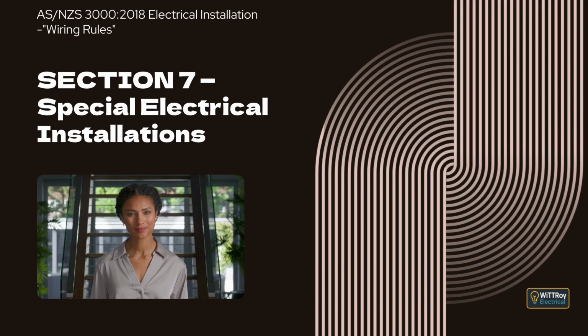Clause 7.2.5.1 General. This clause explains that fire pumps and fire pump control equipment include items such as fire hydrant booster pumps, pumps for automatic sprinkler or spray or deluge systems, pumps for fire hose reels where they are the sole means of fire protection, fire pump control equipment and wiring systems, and fire pump rooms. It also explains that there may be other fire and smoke control equipment not listed. An exception is explained, stating that the requirements of Clause 7.2 do not apply to electrical equipment where failure would not affect the operation of safety services.